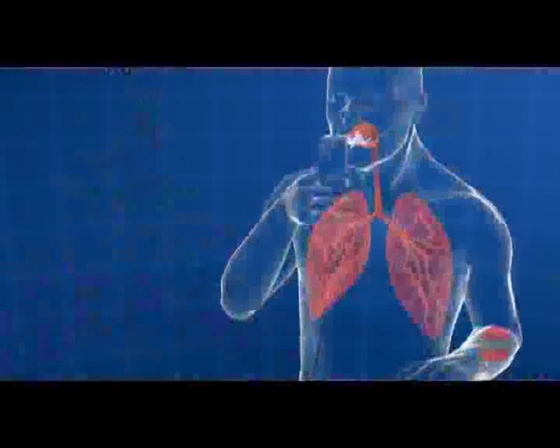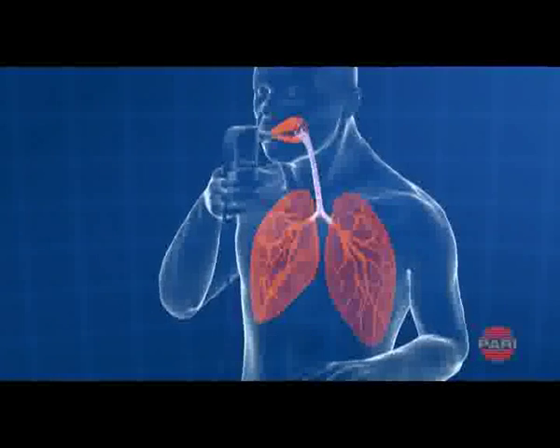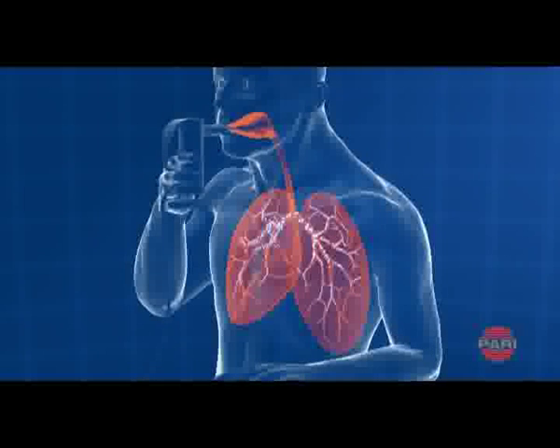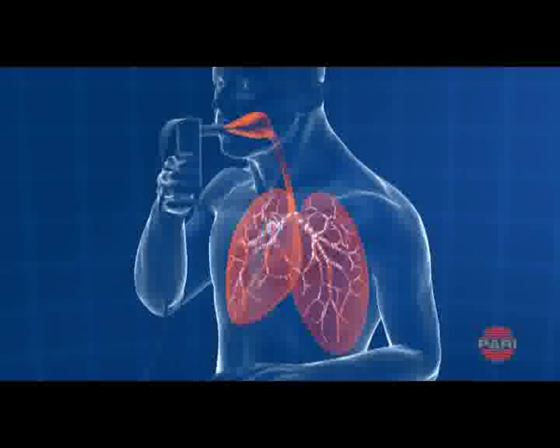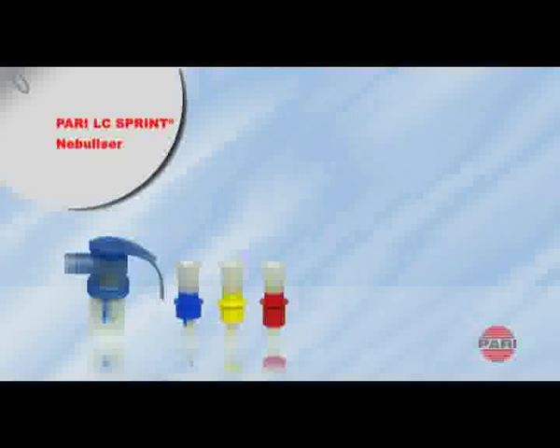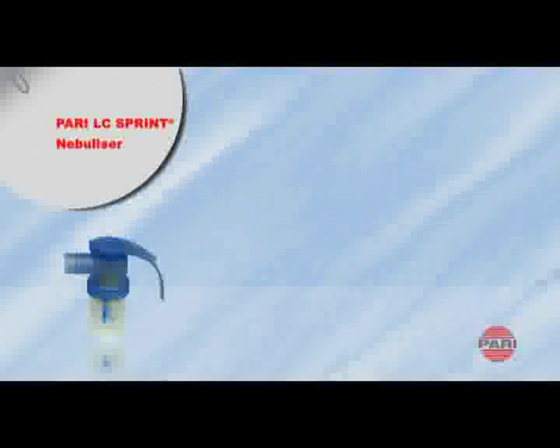The droplets produced vary in size depending on the design of the nozzle attachment. The size of the particles determines which part of the lung is reached by the aerosol. This ensures that it targets the exact place where its effect is required. This is why PARI has developed three nozzle attachments, each being designed with the patient's age or the application in mind.